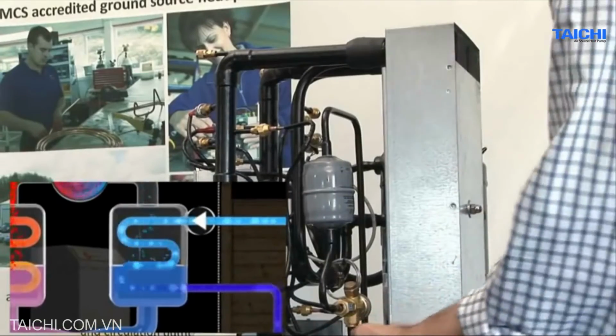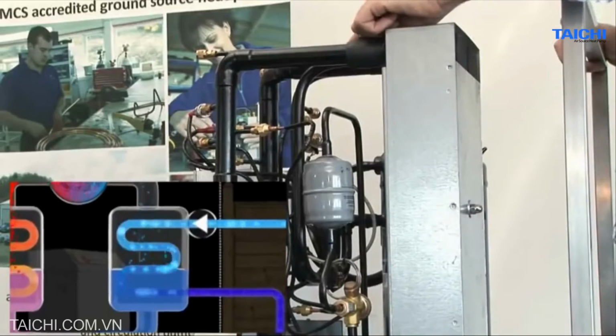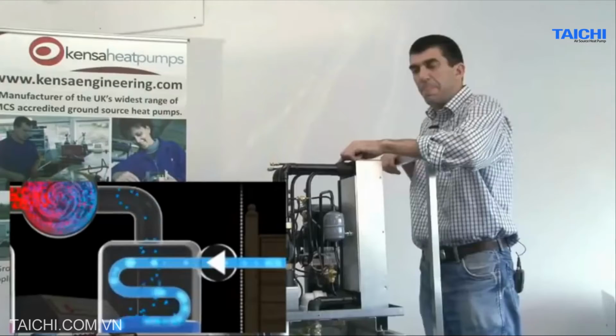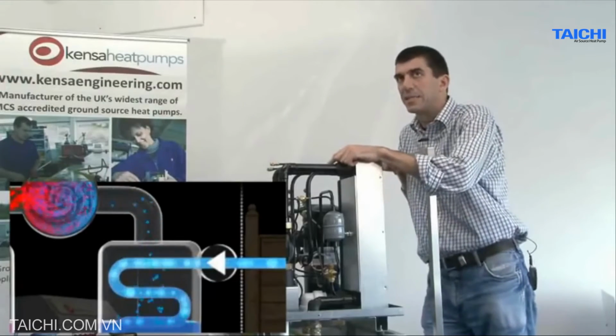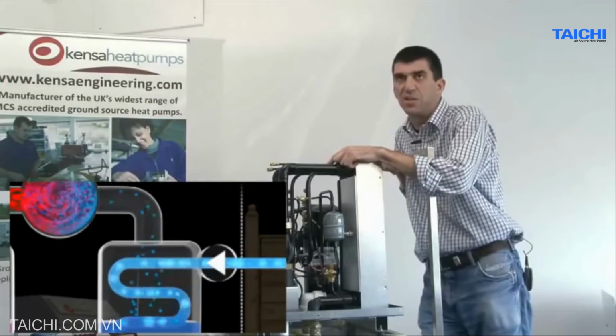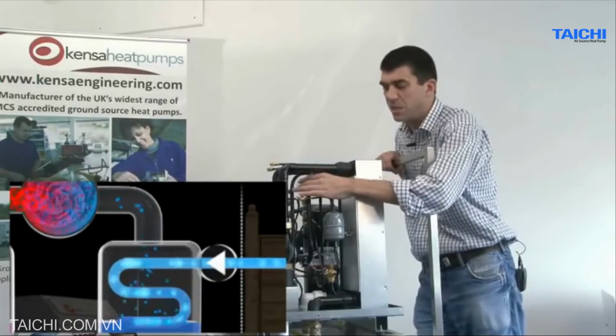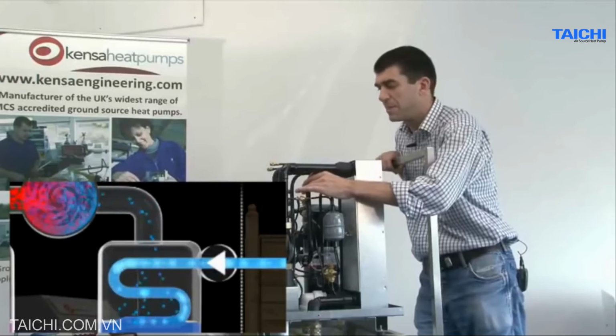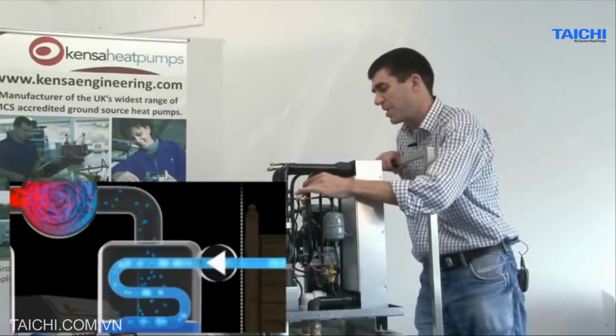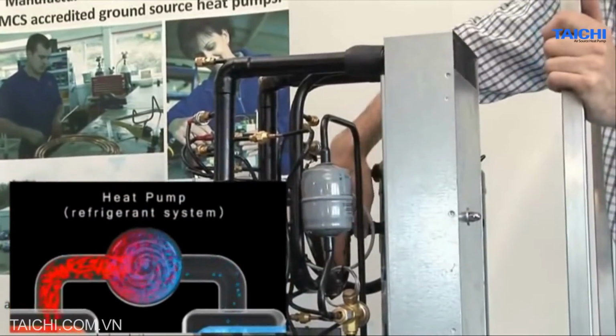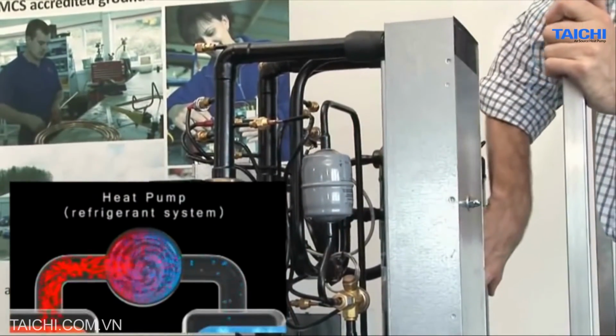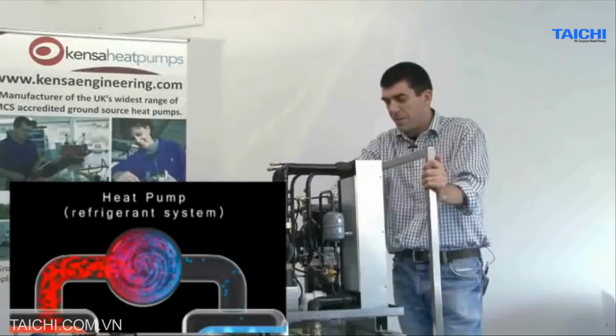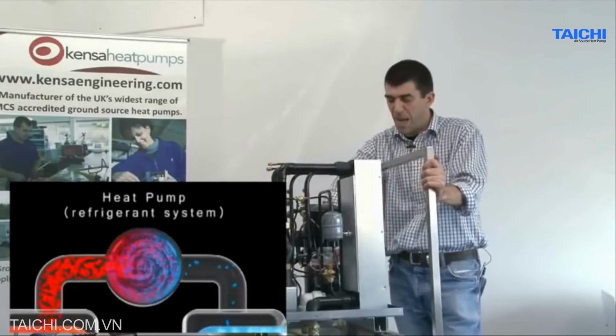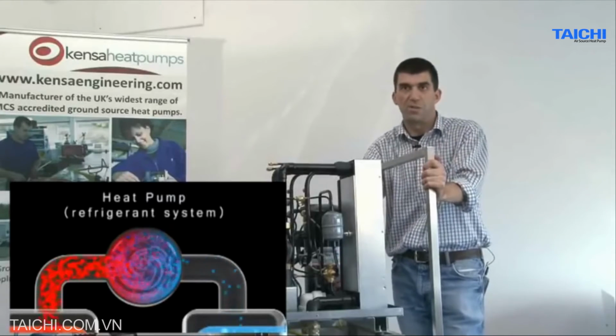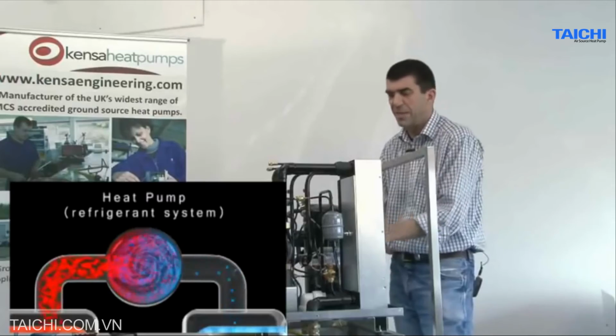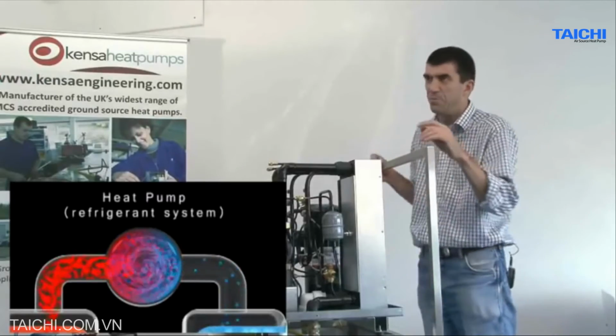And our gas, which enters at the bottom as a liquid, emerges from the top of the heat exchanger fully vaporized, containing the latent heat that's made it change its state. So although it's not warm to the touch, this pipe is probably only 3 or 4 degrees above freezing, it actually contains a lot of thermal energy. That gas passes back to the compressor on the larger diameter pipe and is drawn into the body of the compressor. Here it does another little useful function. It gets passed over the electric motor and cools the electric motor, so the motor has no requirement for any external cooling. It's purely internally cooled by the gas.